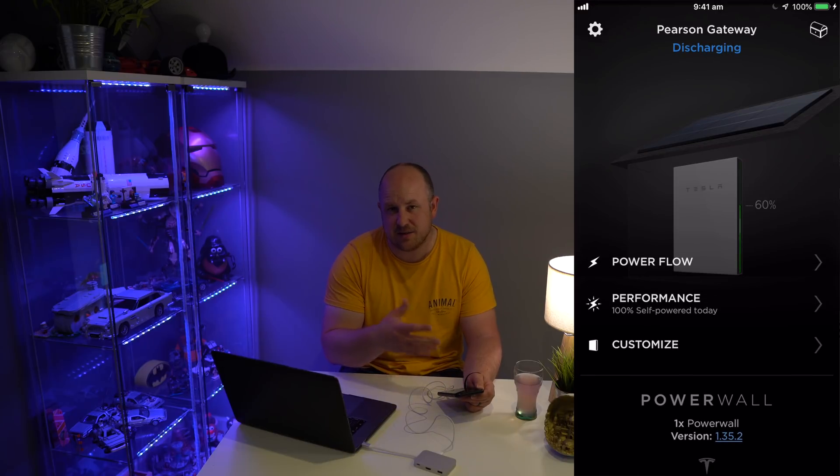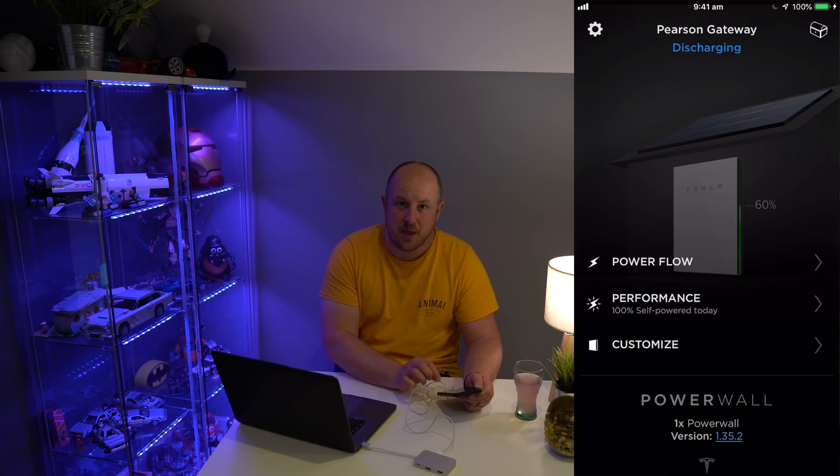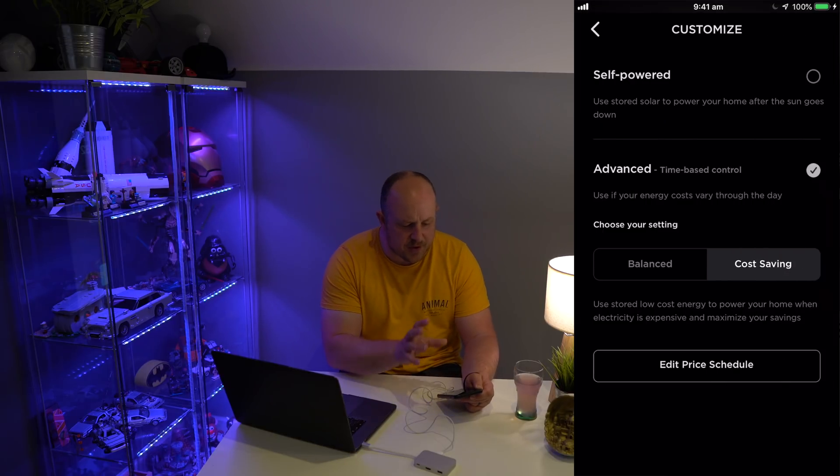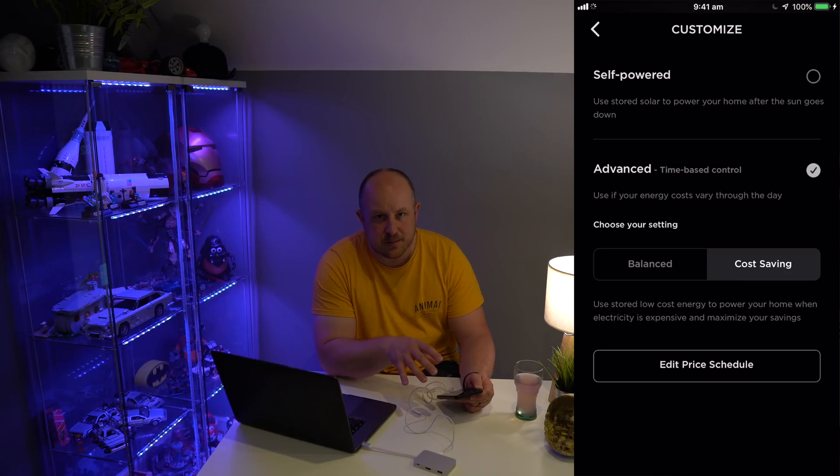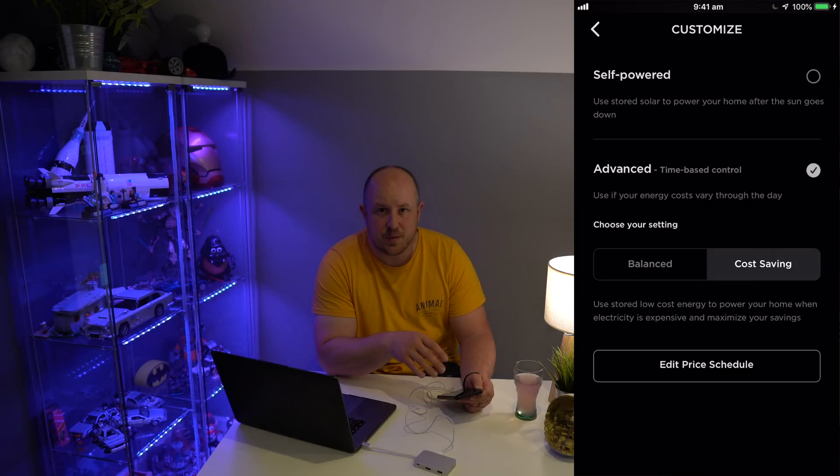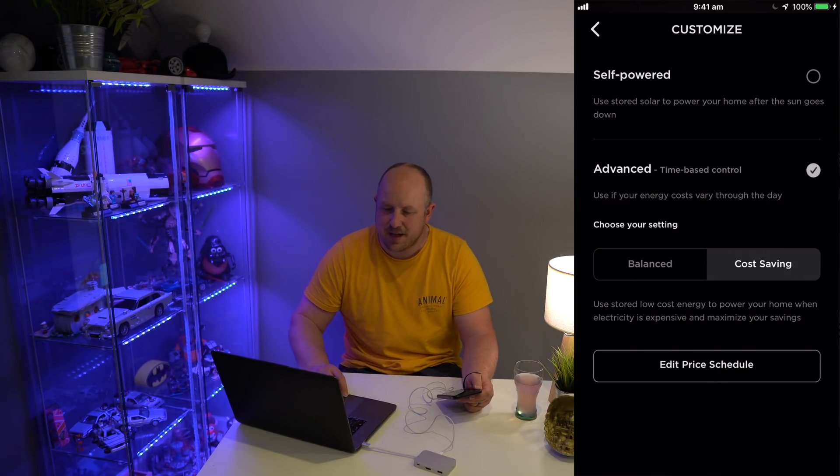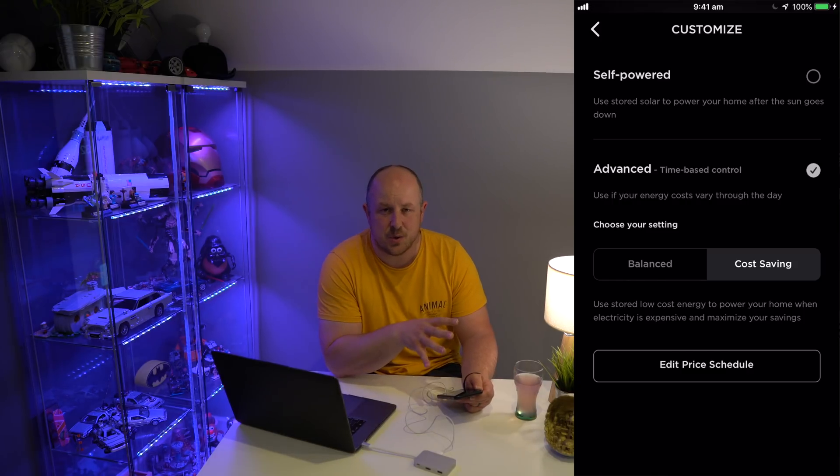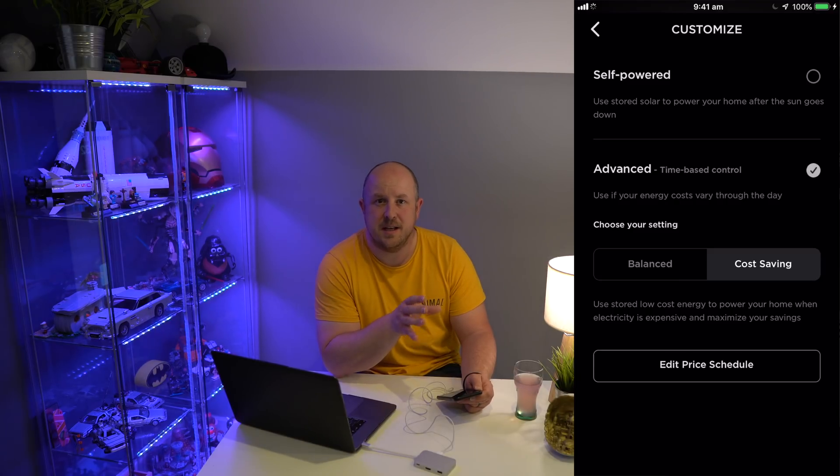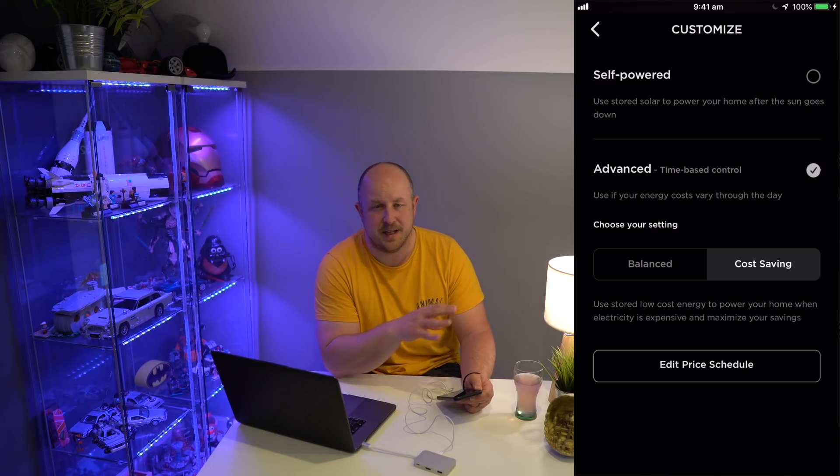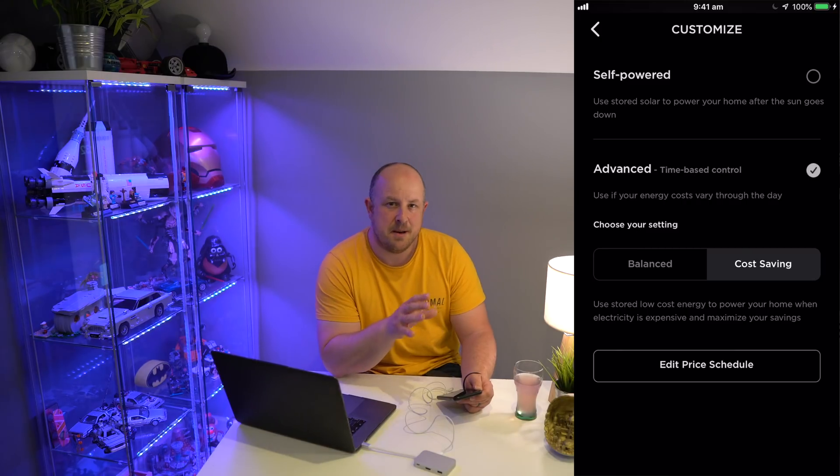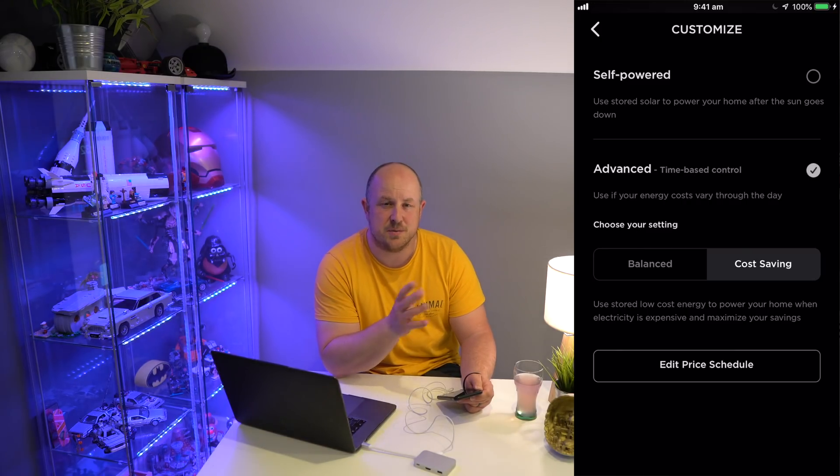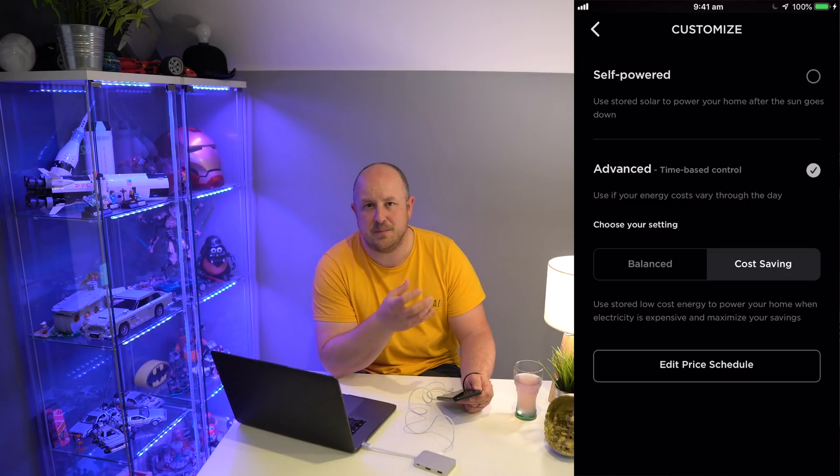For reference, I'm currently running version 1.35.2. If you have the Gateway 2, I know you have an option for Backup Only. Basically what that does is 100% of the energy stored in the Powerwall 2 is only utilized if there is a power outage, and your house will fall back to running off the battery. It's not going to use it for anything else.